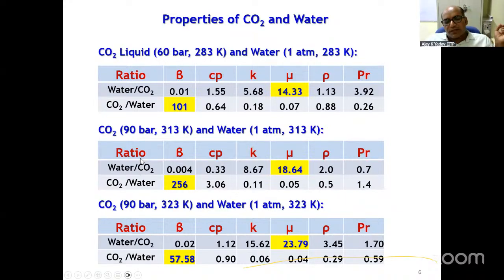If you compare in the supercritical, this is liquid, so subcritical, now compare the supercritical side. So why is supercritical advantageous? Just you can see here, the ratio part beta is much more than liquid stage, and in the supercritical state you can see the difference is 256 times, very high, and Cp is also very high, 3 times water's. So Cp is a very important part. If you have higher Cp, your heat carrying capacity will be more. For 1 degree temperature difference, it will carry 3 times higher heat than water.